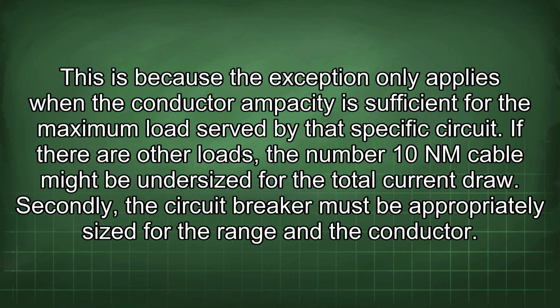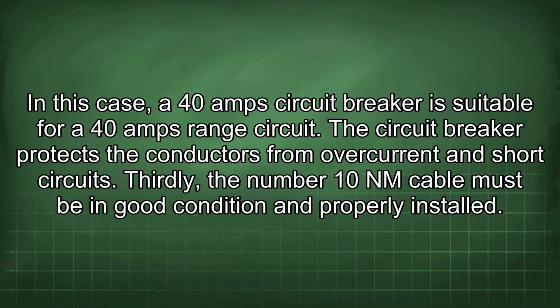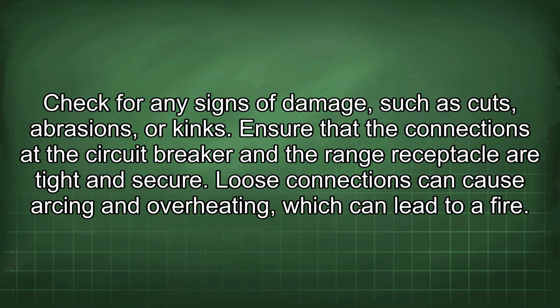Secondly, the circuit breaker must be appropriately sized for the range and the conductor. In this case, a 40 amp circuit breaker is suitable for a 40 amp range circuit. The circuit breaker protects the conductors from overcurrent and short circuits. Thirdly, the number 10 NM cable must be in good condition and properly installed. Check for any signs of damage, such as cuts, abrasions, or kinks. Ensure that the connections at the circuit breaker and the range receptacle are tight and secure. Loose connections can cause arcing and overheating, which can lead to a fire.